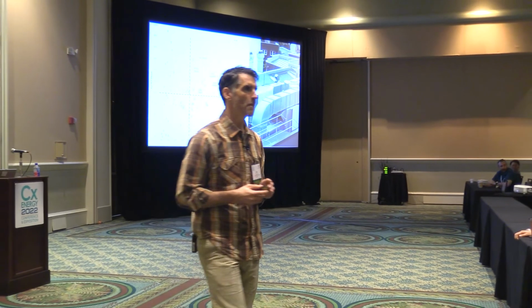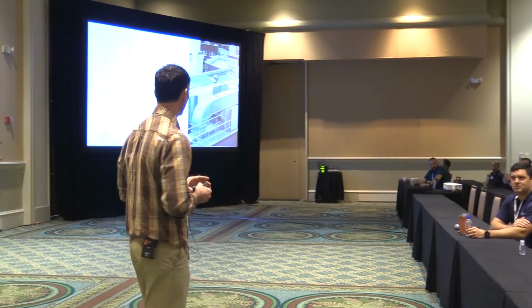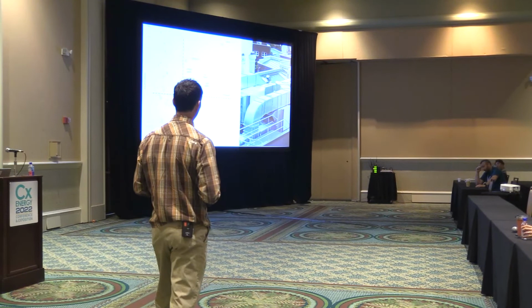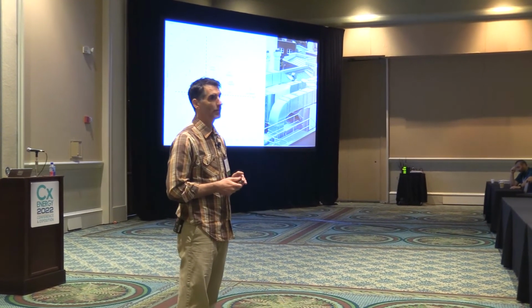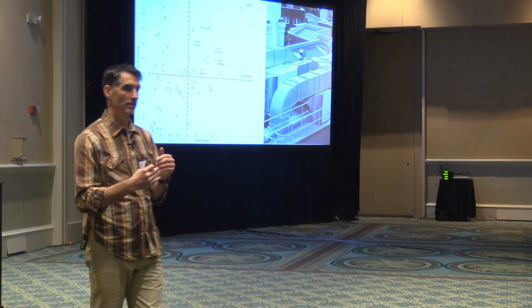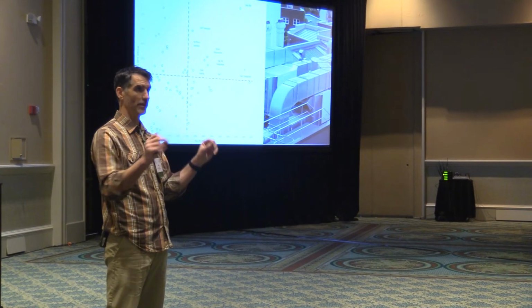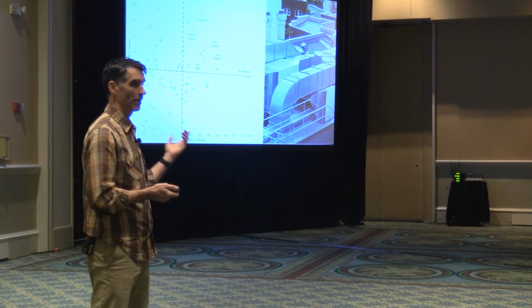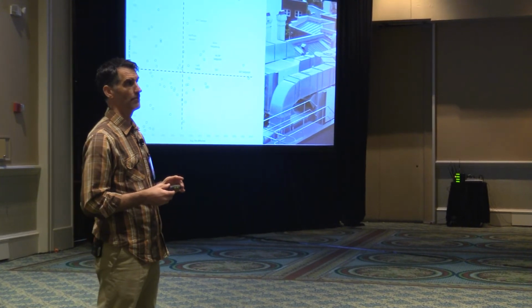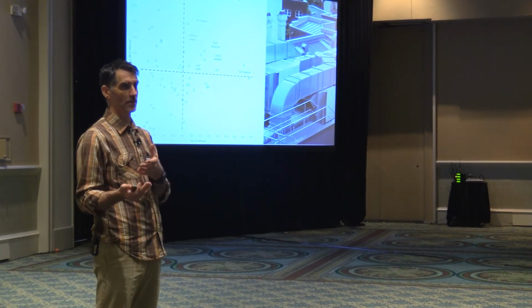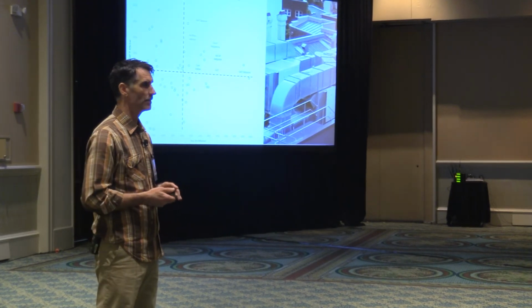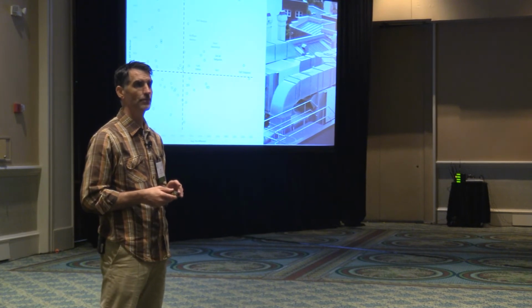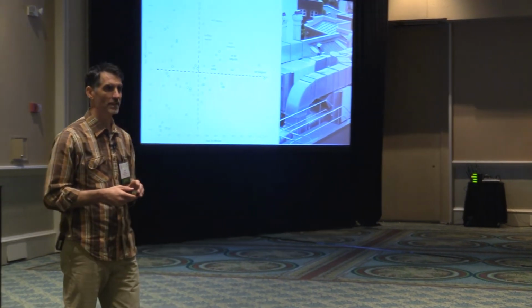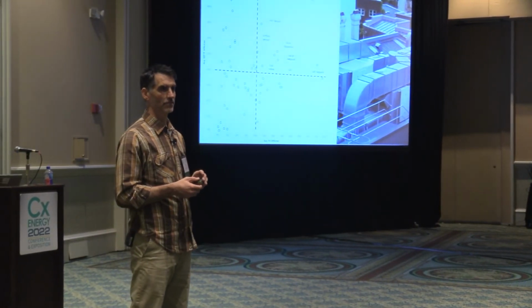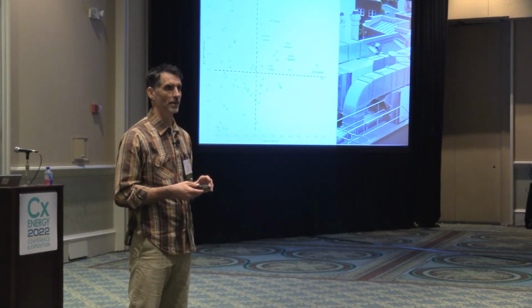Would manual overrides be captured, and how would they show up on this? That's a good question. I think they'd show up in different places. Looking at our list of discrete faults, we don't have one specifically called manual override. It could show up as a set point fault, saying the set point has been constant for too long, if the software knows the programming says it should vary. So that issue is kind of hidden below the surface. Similarly with scheduling faults, we don't necessarily report that it's the schedule—it just flags the set point for review.